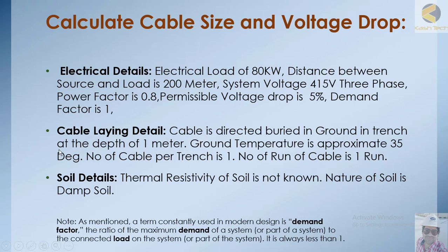The cable installation detail: cable is direct buried in ground in a trench at a depth of 1 meter. Ground temperature is approximately 35 degrees. Number of cables per trench is 1, number of runs per cable is 1. The thermal resistivity of soil is not known and the nature of soil is damp.